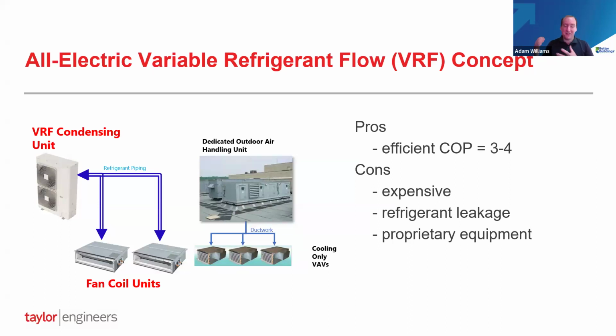The problem with this is the building was not designed with fan coils in mind. So the whole hot water piping distribution would have to be taken out and replaced with brand new refrigerant piping distribution, and retrofitting all the floors in the building for this VRF solution proved to be very expensive. Other concerns with VRF is you have a whole building's worth of refrigerant charge. And if that leaks into a space, that can be a health and safety concern. Now, the refrigerants aren't generally toxic, but there could be enough volume dumped in a space to displace enough oxygen that there could be a health and safety issue. Also, at the time of designing this, it would be designed with R410A, which is a high greenhouse gas emitter, and refrigerant leakage is more likely with field installed piping. So, it is a fair concern.